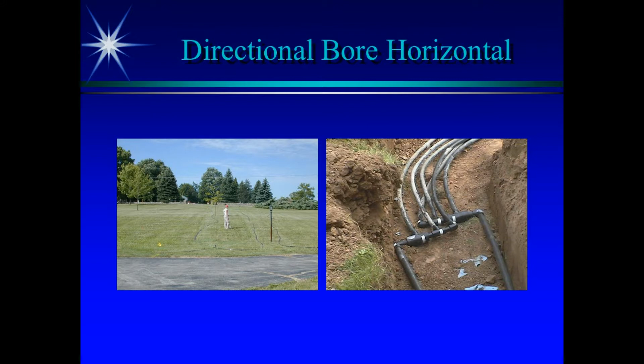We can use your existing well, provided it's big enough and has good quality water. Up here you usually have a lot of good quality water, but when you get down into the Flint, Lapeer, or Monroe areas, it's nasty. You can't do it, it clogs up the heat exchanger with iron and other stuff, and the maintenance to keep it clean is crazy, so they have to go with closed loop. Up here, once you get to Houghton Lake North, we can still do open loop, and in fact there are still more open loops from Houghton Lake North than closed loops. But south of that, almost everything is closed loop.